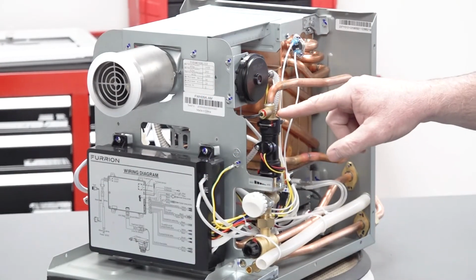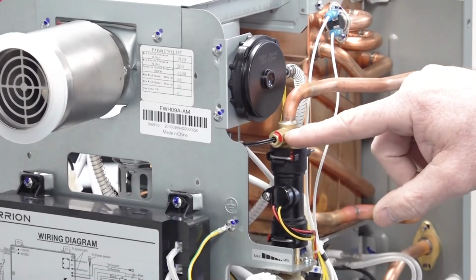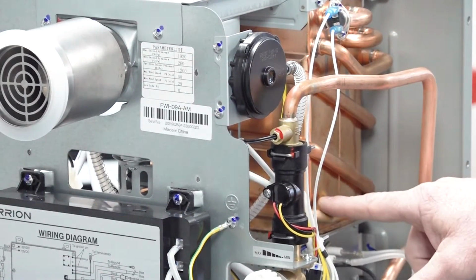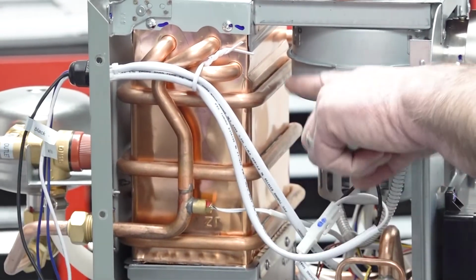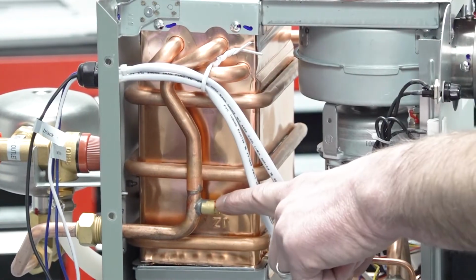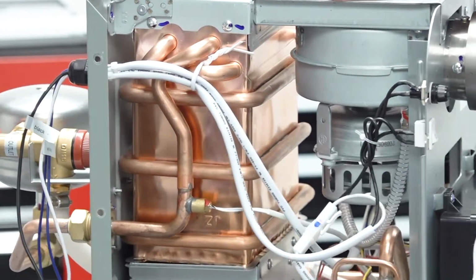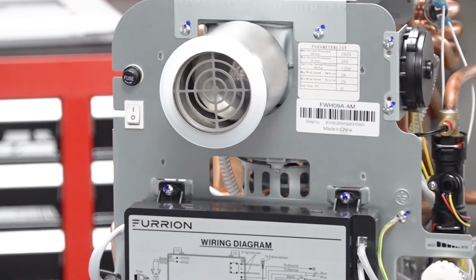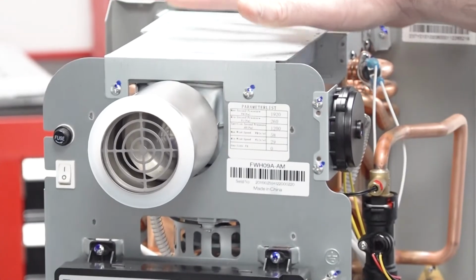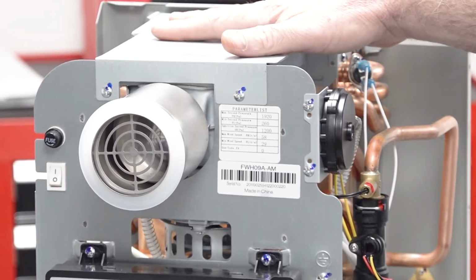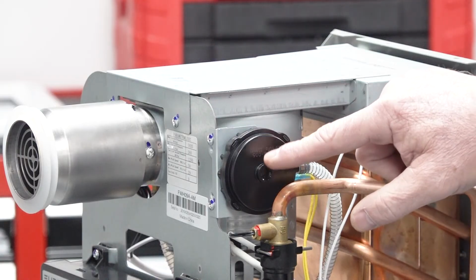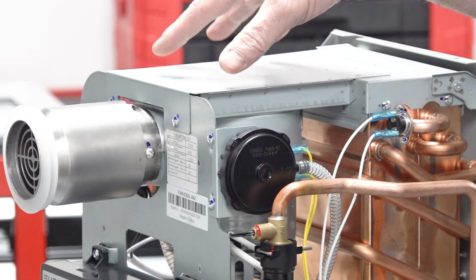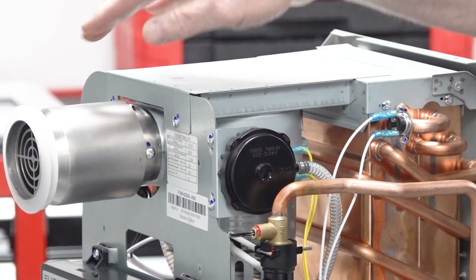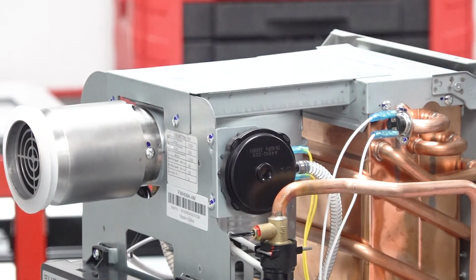I also wanted to point out the dual over temperature sensors. This one is on the inlet of the water before it gets heated up by the heat exchanger. And the second one is here after the water goes through the heat exchanger and heats up before it exits the appliance. Those dual over temperature sensors will shut the water heater down if a safe water temperature is exceeded. We also have the exhaust pressure switch that monitors the flue fan assembly exhaust pressure and will shut down the water heater if the correct parameters are exceeded.